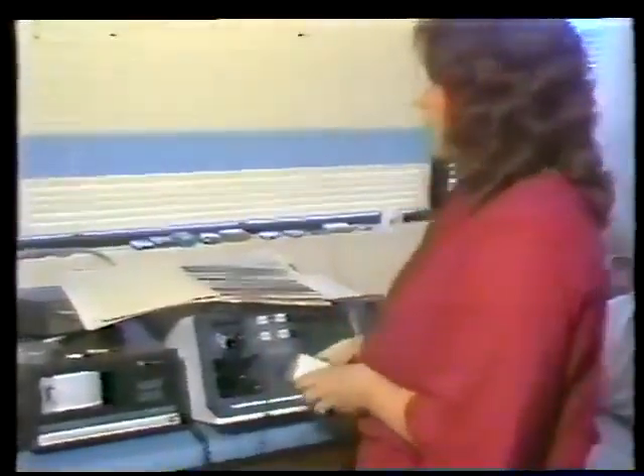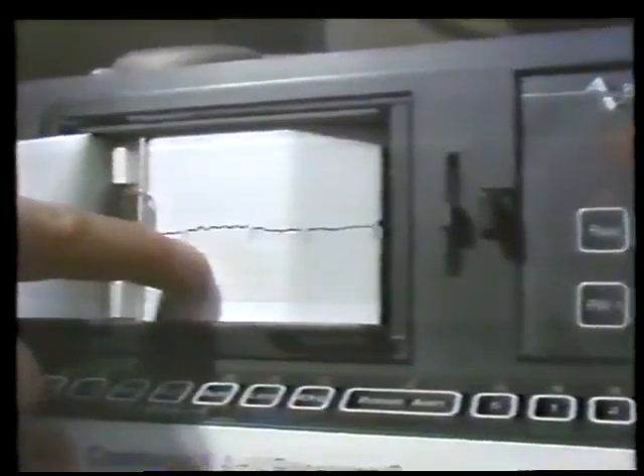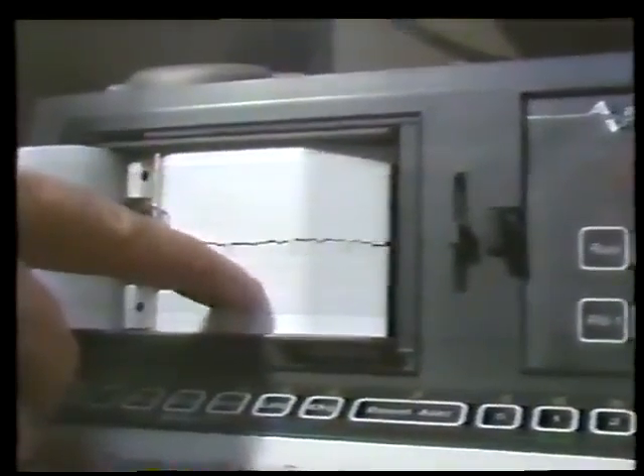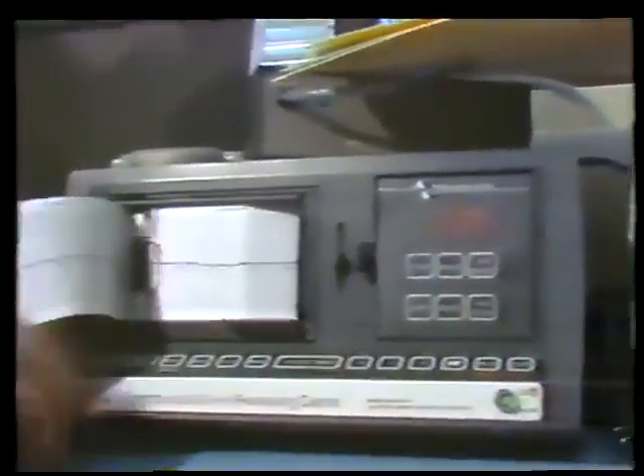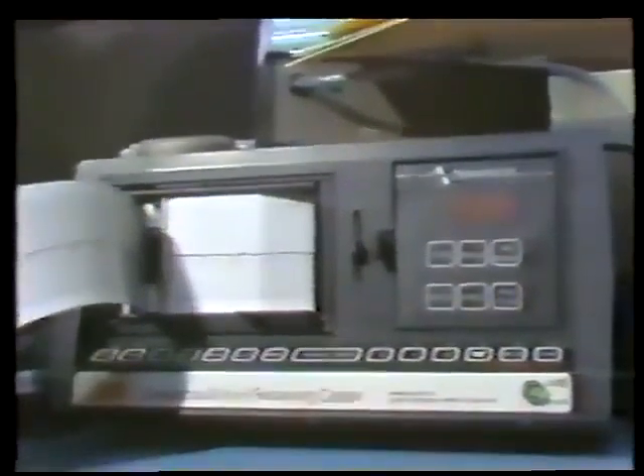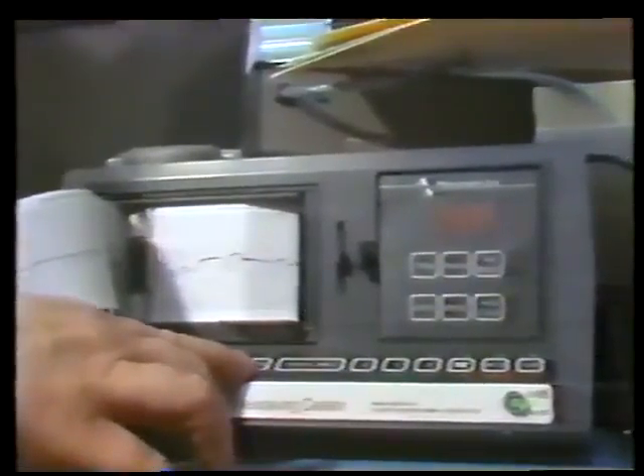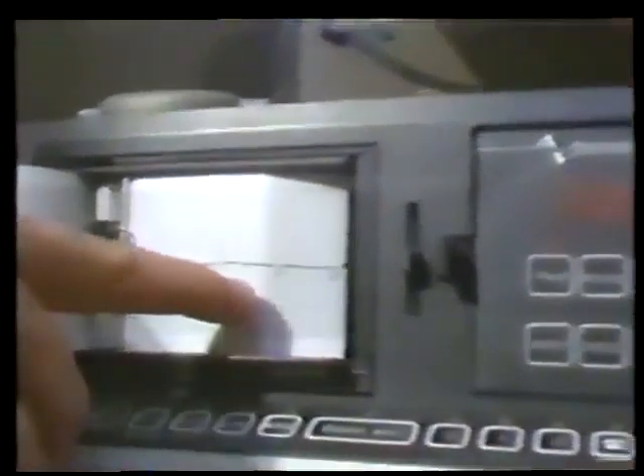We use this apparatus to see how well it really is working. She'll put it on his chest. Okay. We are now seeing a readout of the patient's own electrical activity here. That means the pacemaker is sensing properly, the computer is working properly, and this is a pacemaker spike, which means that the heartbeat went lower than the programmed rate, and the patient's pacemaker worked. And it's sensing and pacing correctly. This is his own heart. That's the pacemaker electricity.